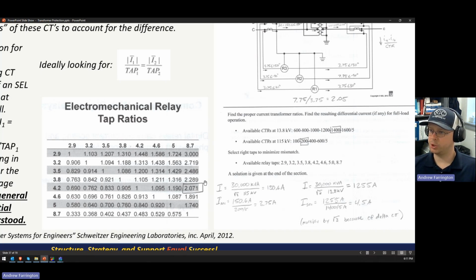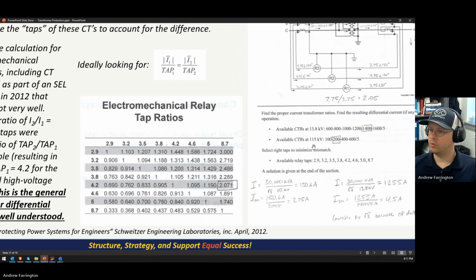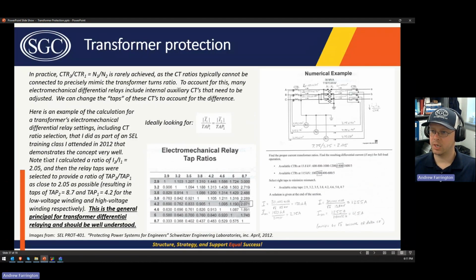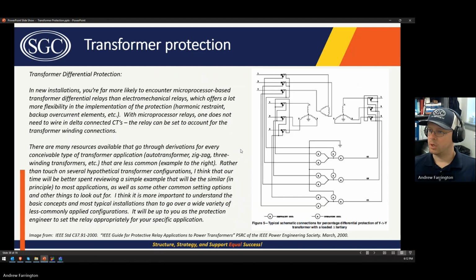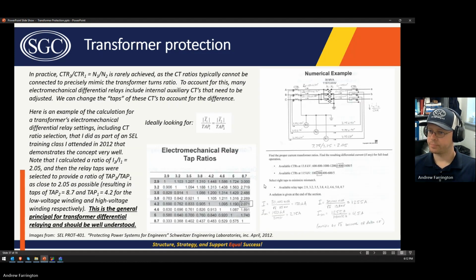So the closest ratio to 2.05 in this case was 2.071, which was a tap 2 of 8.7 and a tap 1 of 4.2. So that was the answer. I kind of wrote that out here. So tap 2 was 8.7, tap 1 was 4.2, and you can then put that back into this equation and make sure that that's the minimum difference, right? This is the ideal, and so you can calculate that mismatch and make sure that you've selected the right ratio of tap 1 to tap 2.